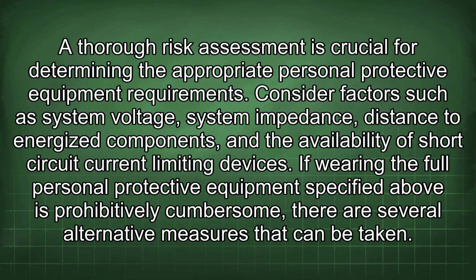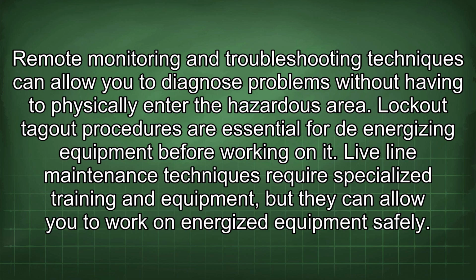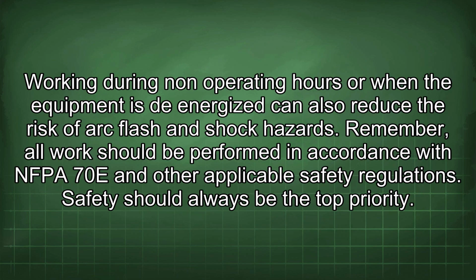If wearing the full personal protective equipment specified above is prohibitively cumbersome, there are several alternative measures that can be taken. Remote monitoring and troubleshooting techniques can allow you to diagnose problems without having to physically enter the hazardous area. Lockout-tagout procedures are essential for de-energizing equipment before working on it. Live line maintenance techniques require specialized training and equipment, but they can allow you to work on energized equipment safely. Working during non-operating hours or when the equipment is de-energized can also reduce the risk of arc flash and shock hazards. Remember, all work should be performed in accordance with NFPA 70E and other applicable safety regulations. Safety should always be the top priority.